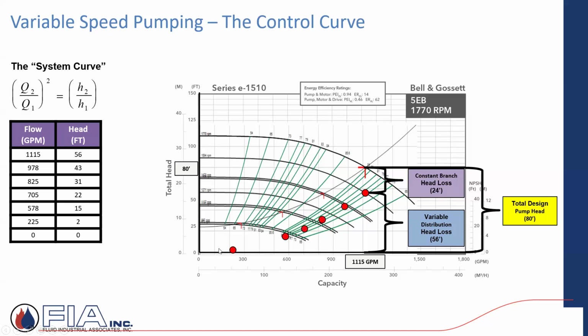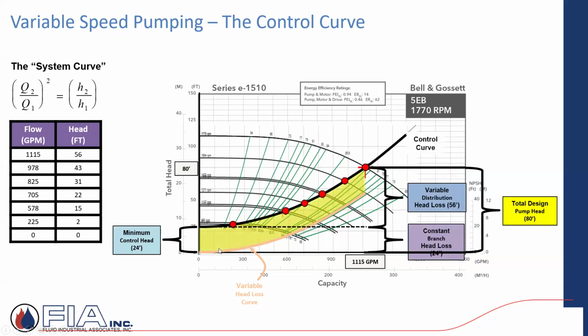So I plug it in and I say, well, this is what that curve looks like, that variable head loss curve, right? But what hasn't this graph over here accounted for? It hasn't accounted for that minimum 24 feet of control head. So in reality, that's what the curve looks like. It's a compilation of both the variable for the distribution, the chillers, the boilers, the pumping, all of that changes, but that control head is a fixed 24 feet.